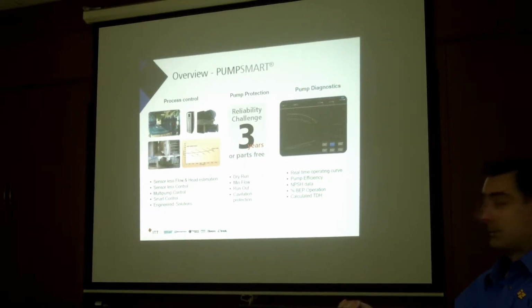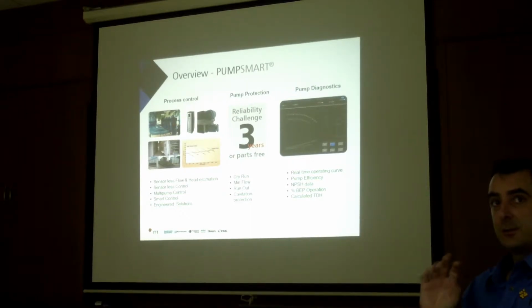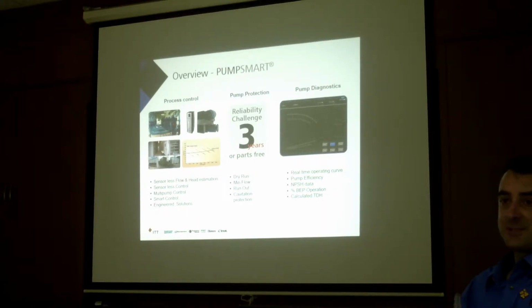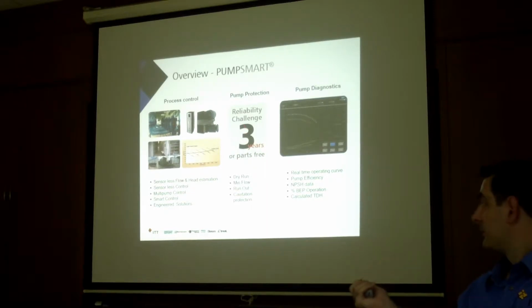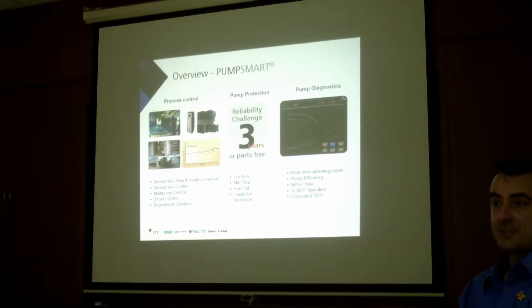our multi-pump control is very, very good. Rather than making two pumps run at the same speed, we'll make two pumps run at the same flow. It's very good when maybe one pump's new and one pump's old. If you have customers with lots of mechanical seal failures in multi-pump systems, it's because of the way they're controlling, even on fixed speed. Two fixed speed pumps are the same as two variable speed pumps running at the same speed, it doesn't matter.